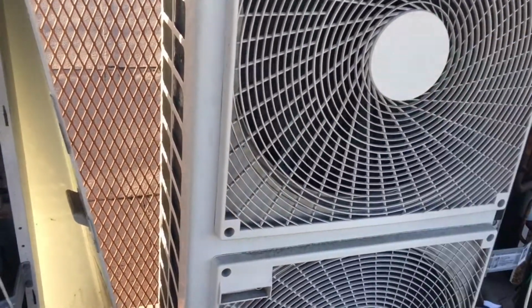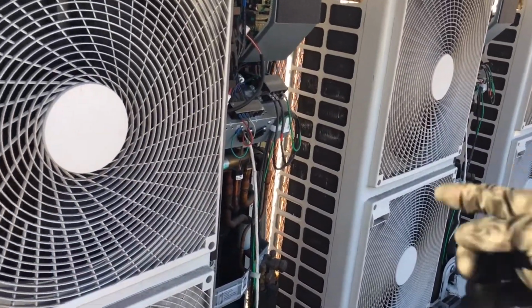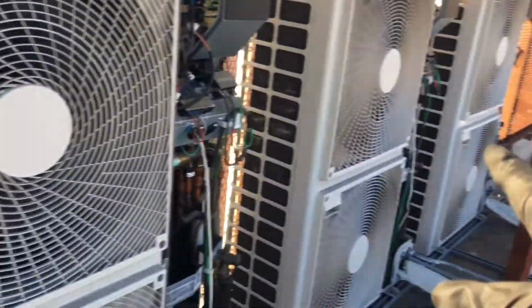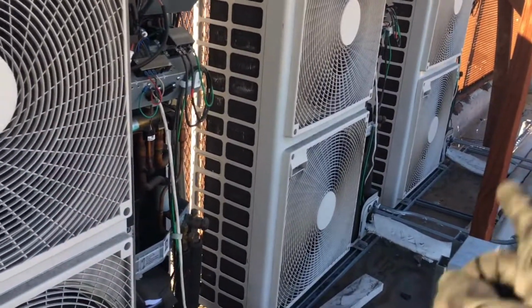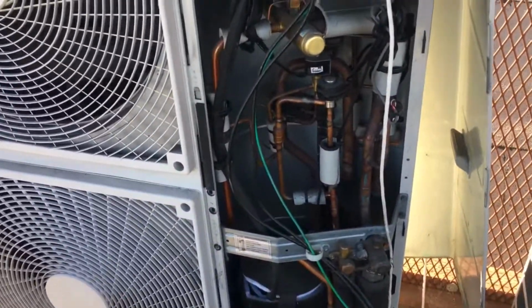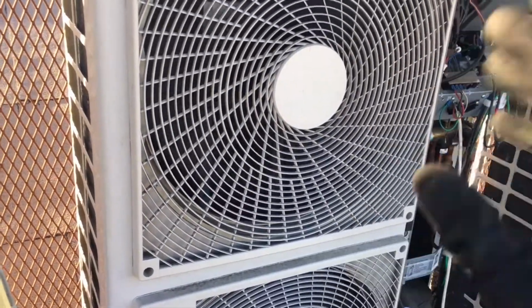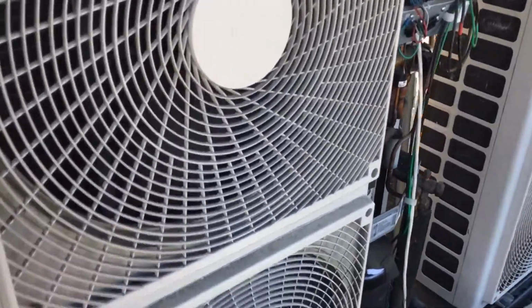So even if one system went completely down, there's a head from another unit inside that room, and then say the heads from this one are in that one, then some in that one, so it's all distributed out, redundant. So even if one system completely failed, no part of the whole building ever is left without air conditioning. This is done with a combination of dividing up heads between rooms with fans that push air, with inducting, sharing it between rooms, in and out in all the rooms. Kind of an elaborate system, but the redundancy is excellent.